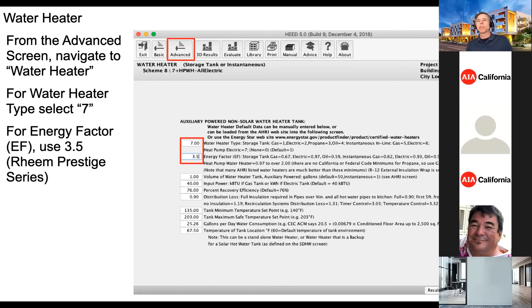The most efficient gas-fired water heater is probably about 97% efficient — 1 unit of energy in equals 0.97 units out, with the remaining 3% lost through combustion up the flue or through the tank. The heat pump water heater has an energy factor of 3.5, thanks to the refrigeration cycle: 1 unit of energy in equals 3.5 units out, so it's 350% efficient.